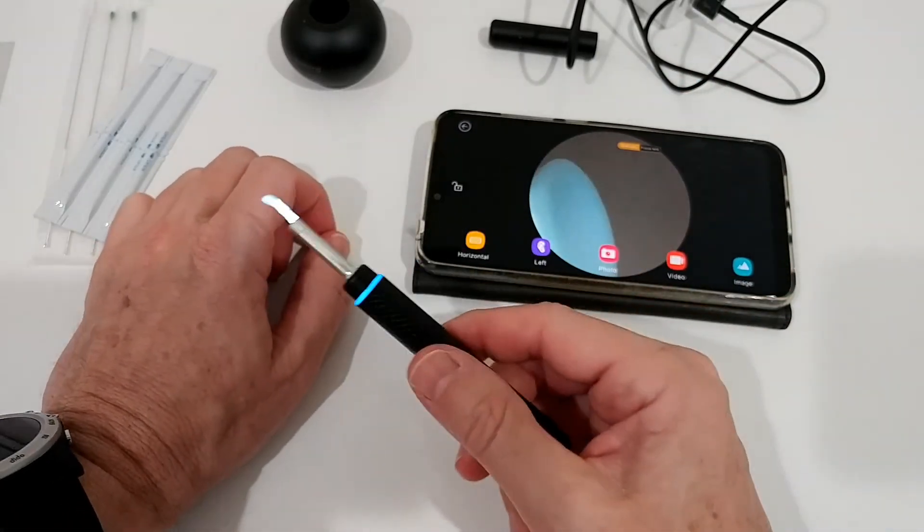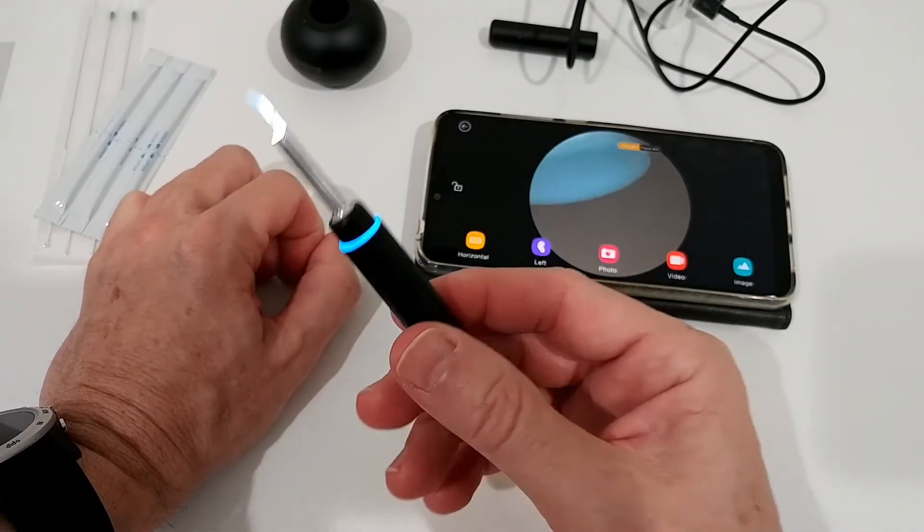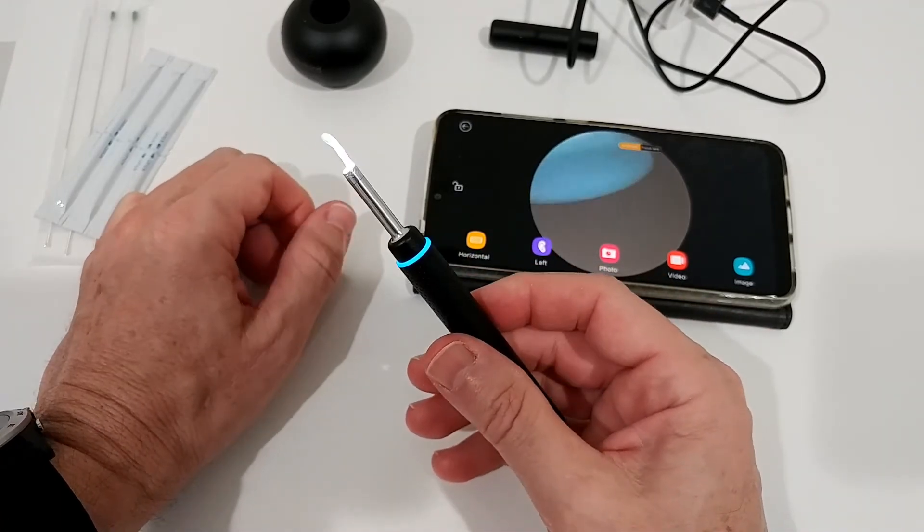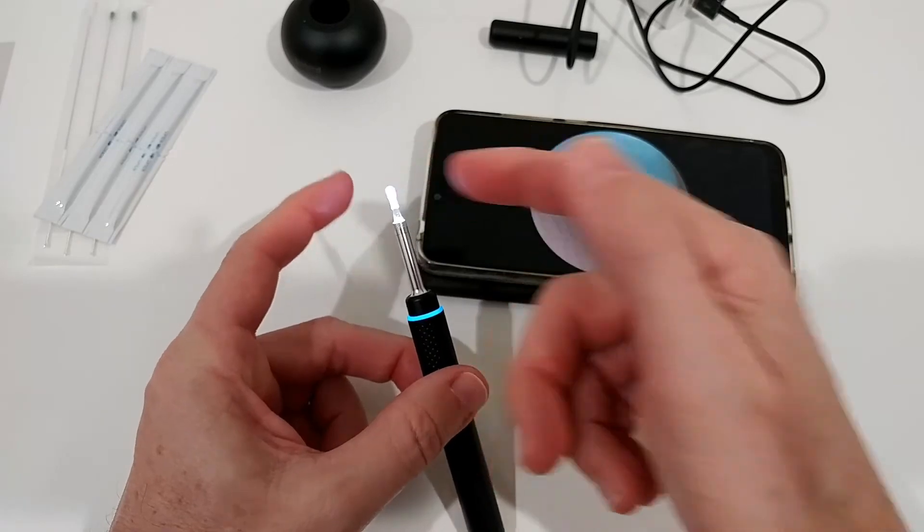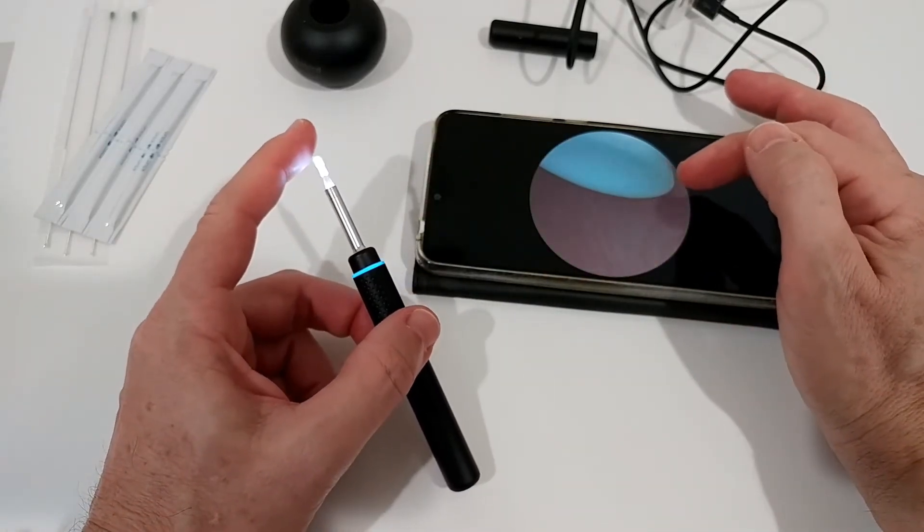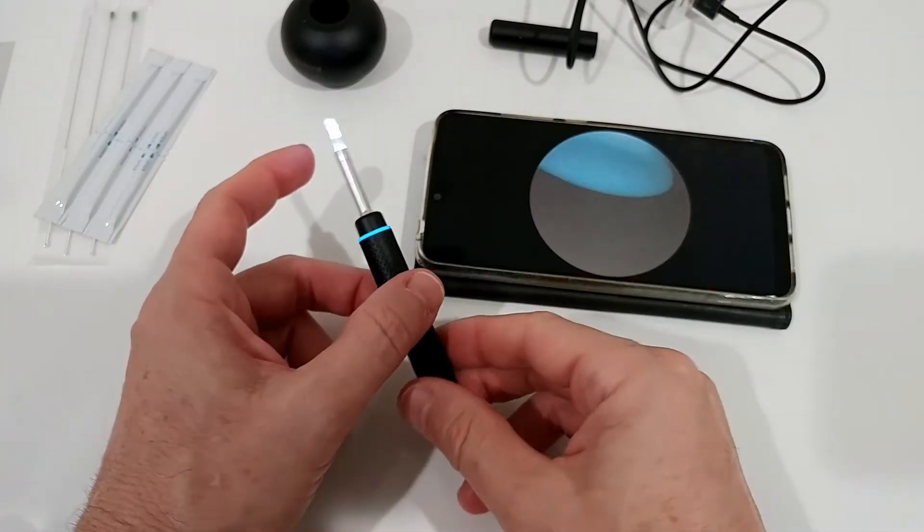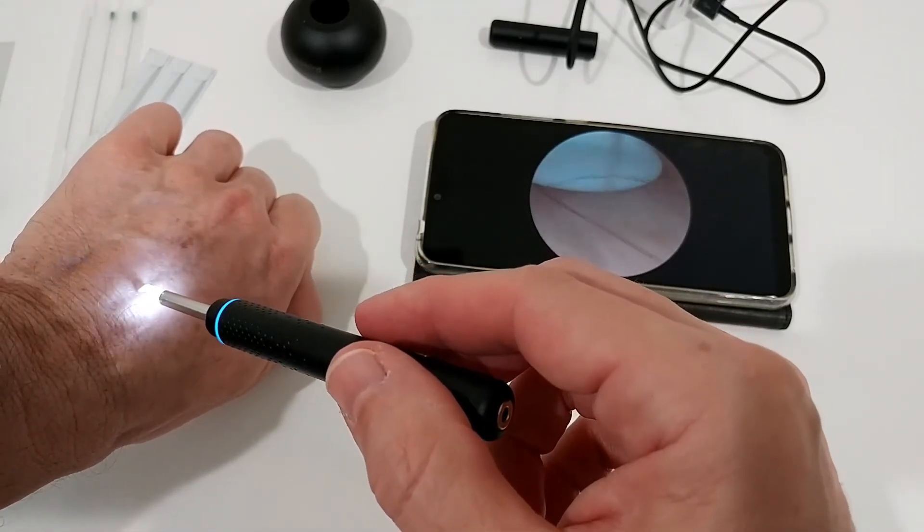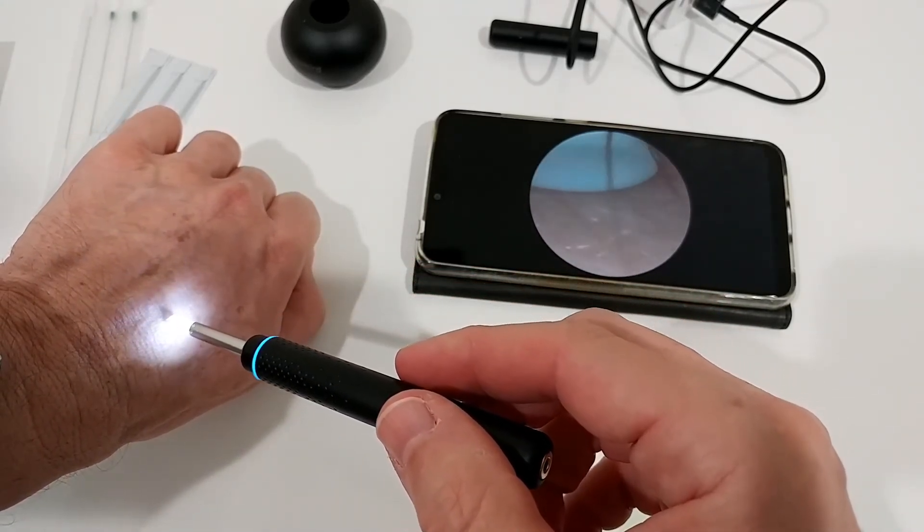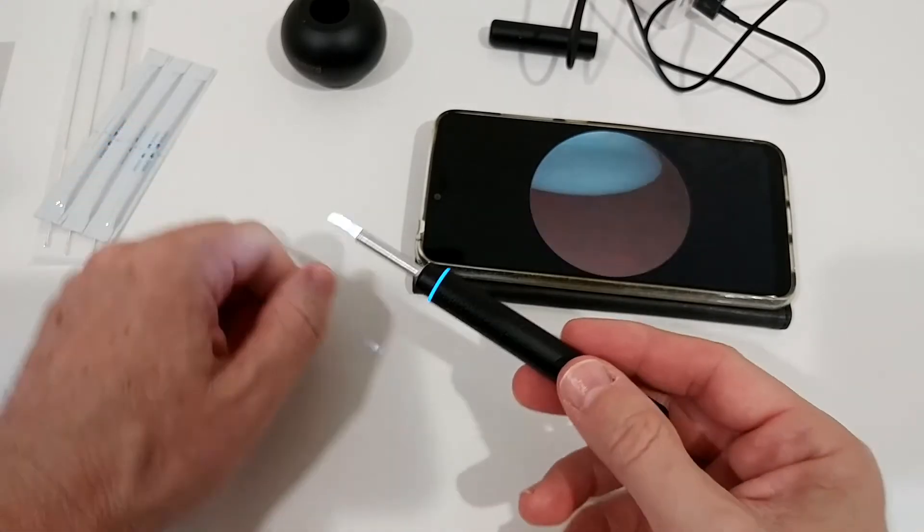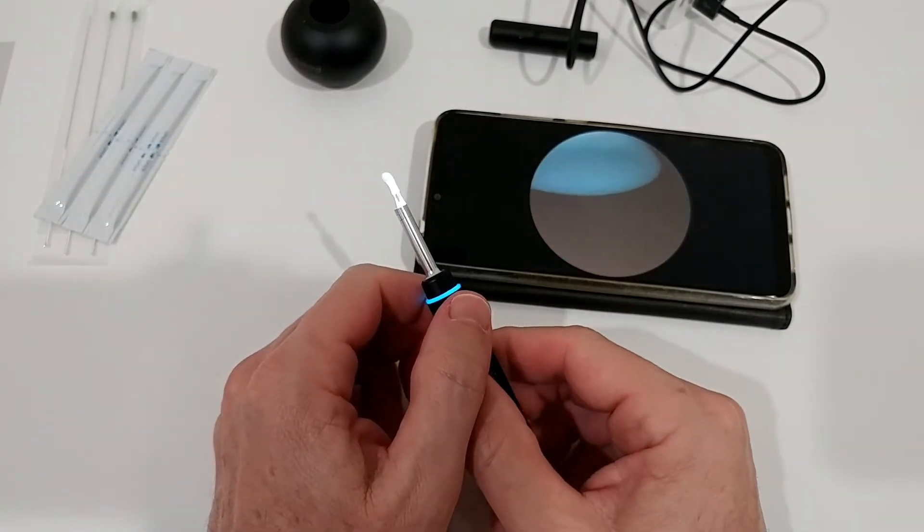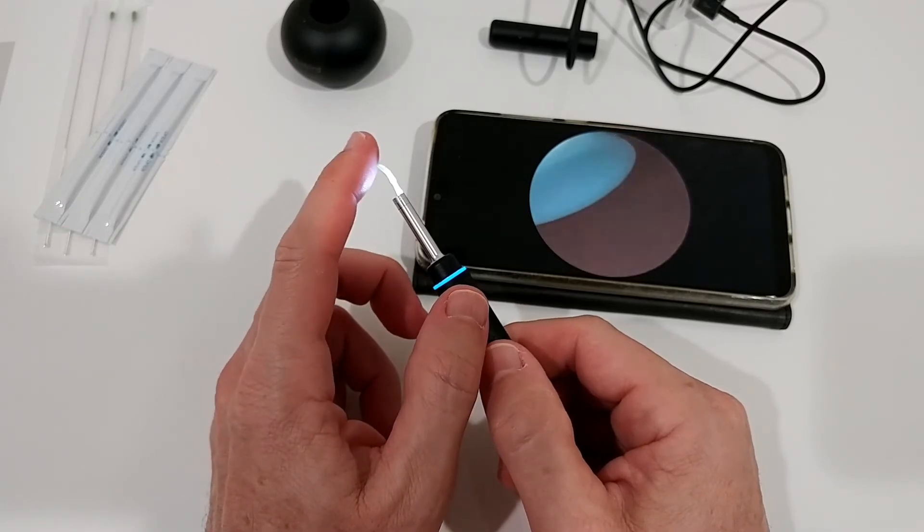What has always been my major concern with this kind of otoscope, they're doing a nice job, but you can see this tip here is blocking almost half of the image. We can still see a lot, it's really nice, but it's still blocking quite some area. But we have to be aware that there's a huge problem if we don't use the tip.